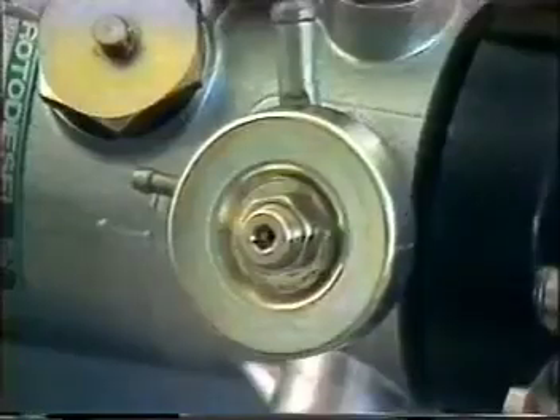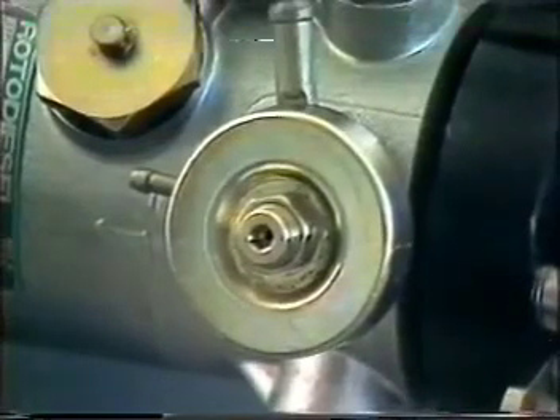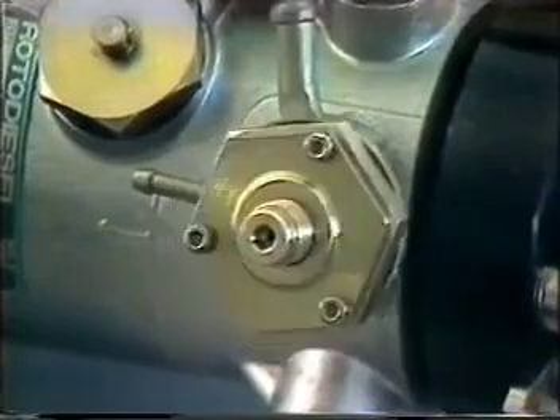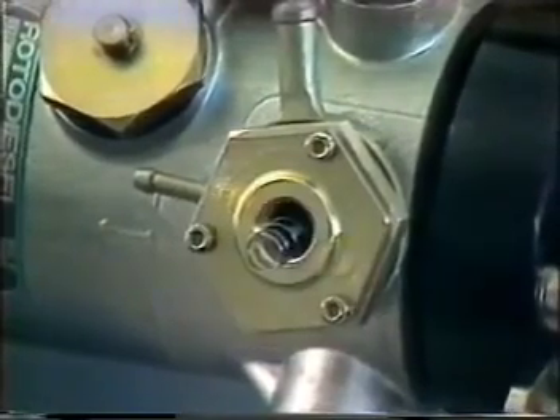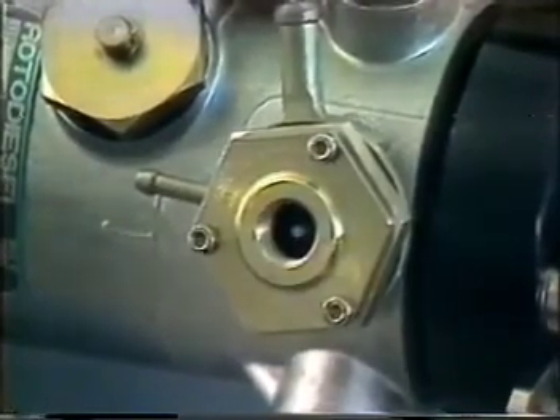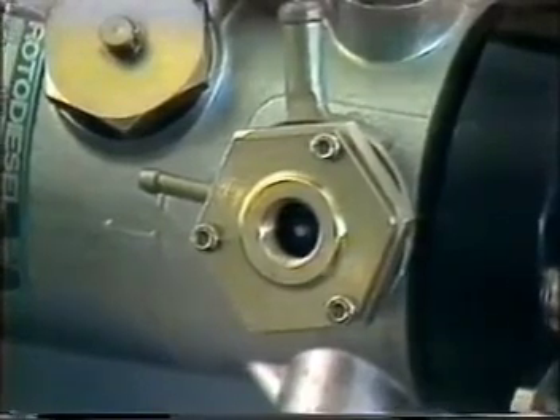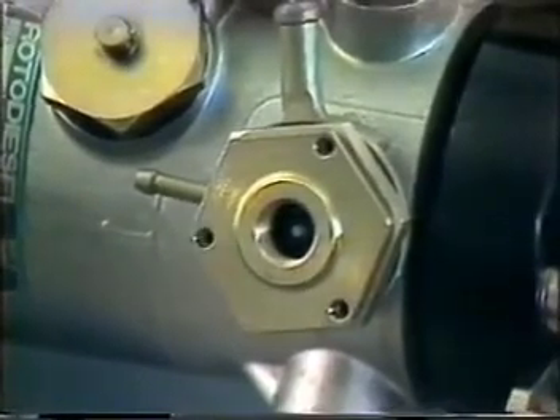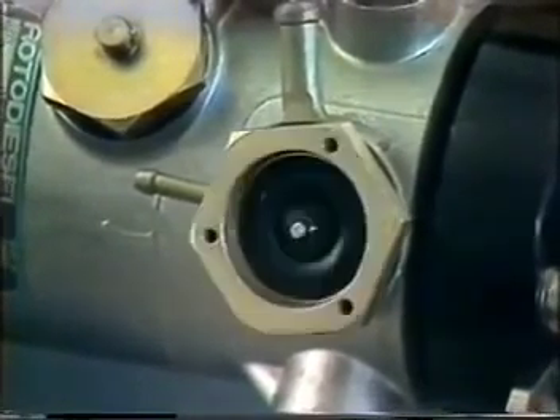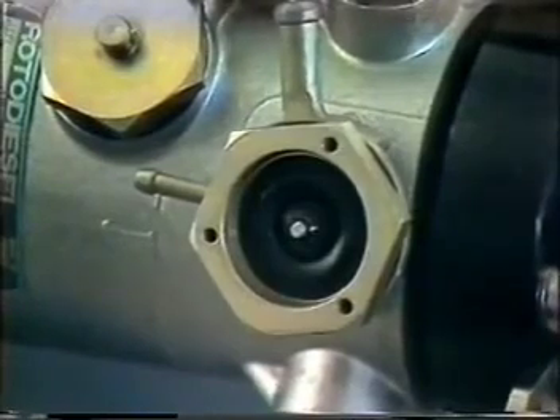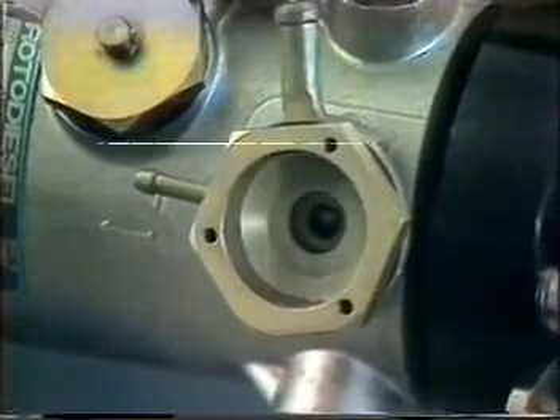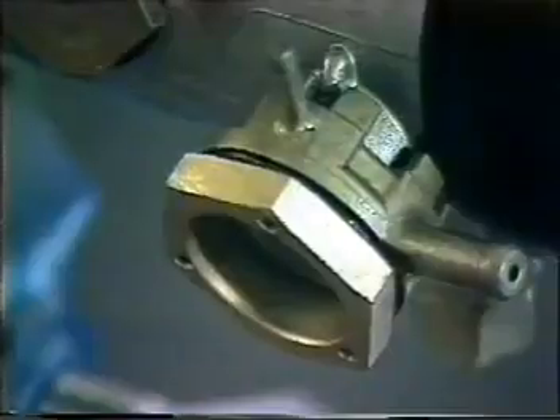Now move on to the pneumatic corrector and start the disassembly. Loosen and remove the locking nut, protector, adjustment sleeve, and spring. Now loosen and remove the 3 screws from the cover, which will allow you to remove it. Remove the membrane and finally loosen and remove the body. The connection cap will also come out.